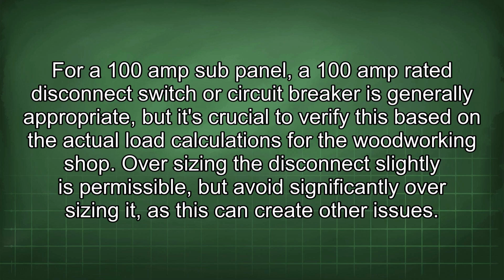For a 100 amp sub-panel, a 100 amp rated disconnect switch or circuit breaker is generally appropriate, but it's crucial to verify this based on the actual load calculations for the woodworking shop. Oversizing the disconnect slightly is permissible, but avoid significantly oversizing it, as this can create other issues.